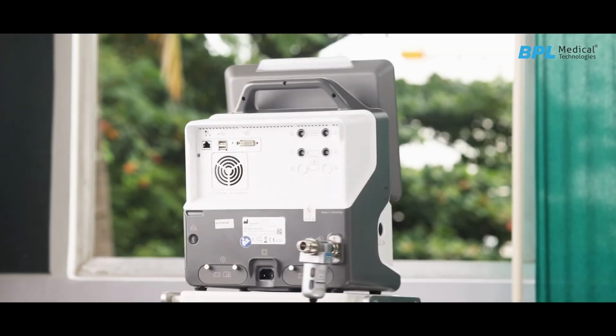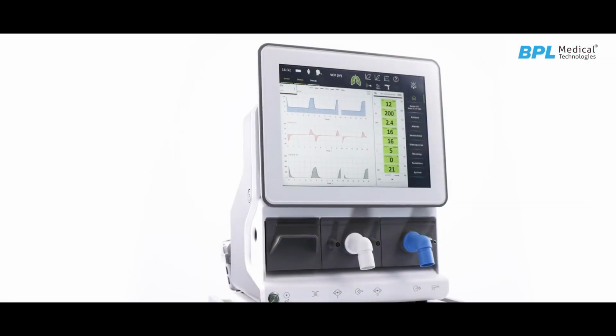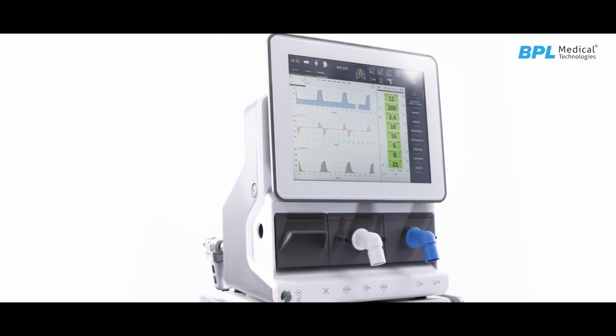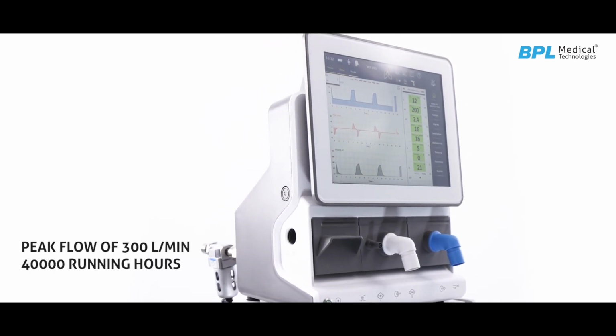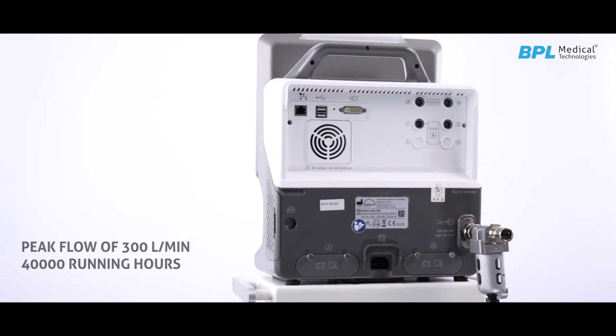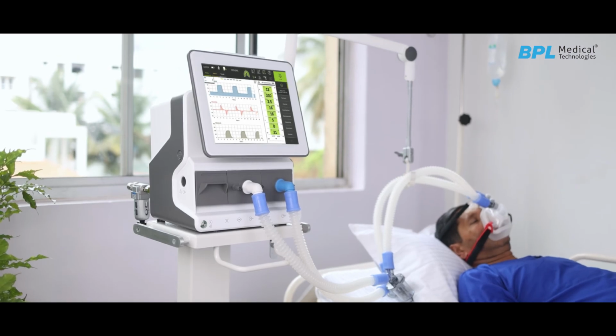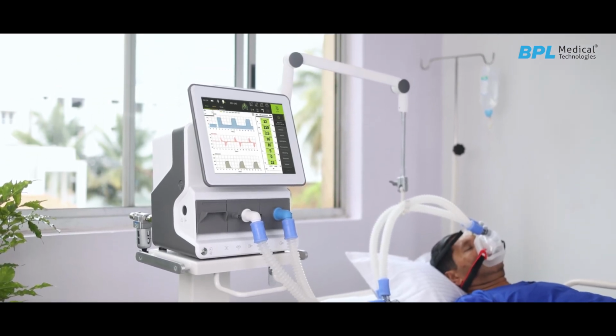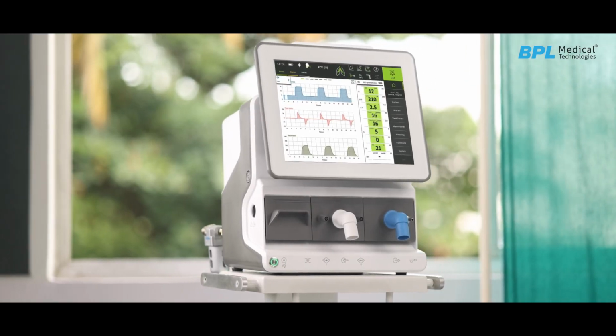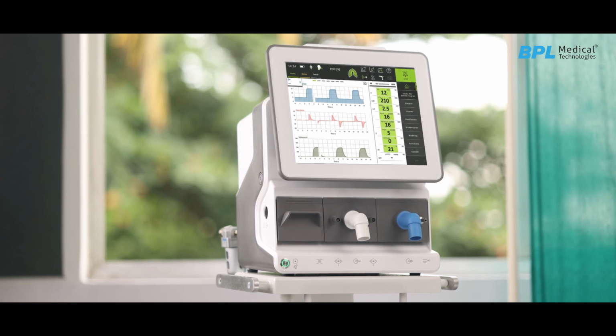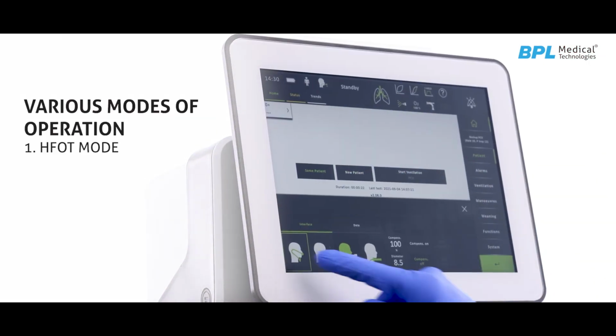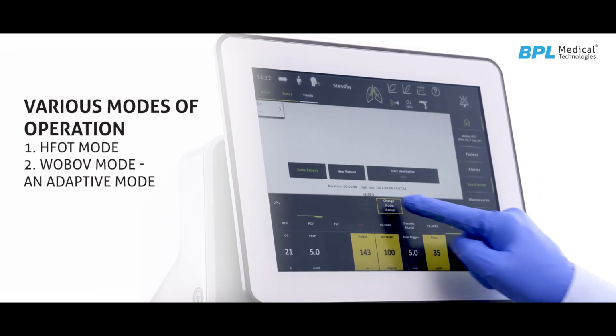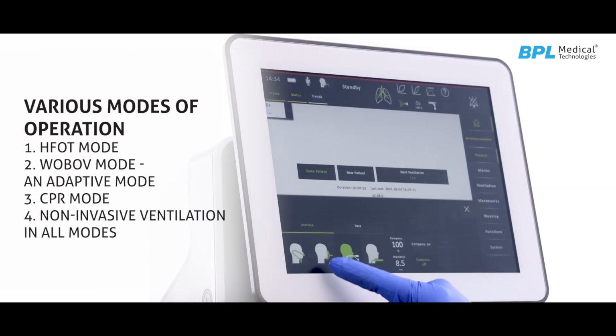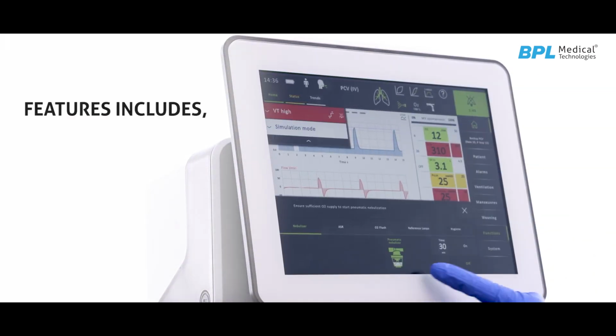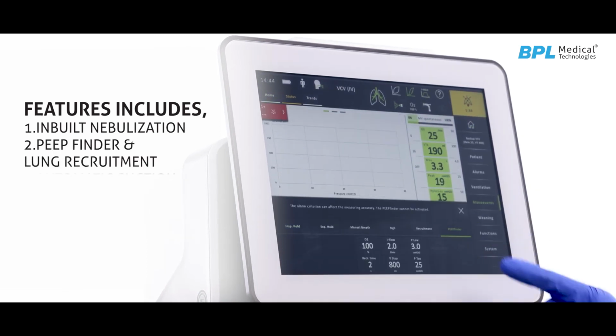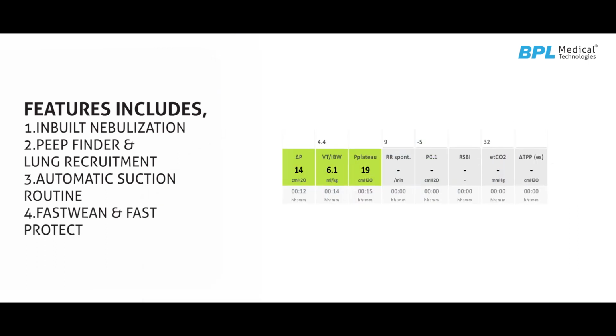Precise, robust and maintenance-free flow sensing technology along with a powerful turbine technology in ELISA 300 enables a maximum peak inspiratory flow of up to 300 liters per minute for up to 40,000 hours at 46 dB. Also, ELISA 300 can measure expiratory data of all patient categories without physically changing the sensor. In addition, ELISA 300 can also be used in various modes of operation depending on the patient need: HFOT mode, WOBOV mode, adaptive mode, CPR mode, and non-invasive ventilation in all modes. Features include inbuilt nebulization, PEEP finder and lung recruitment, automatic suction routine, fast wean and fast protect.